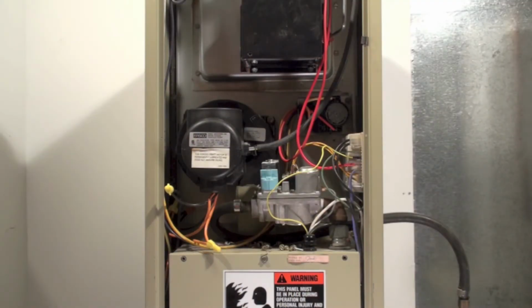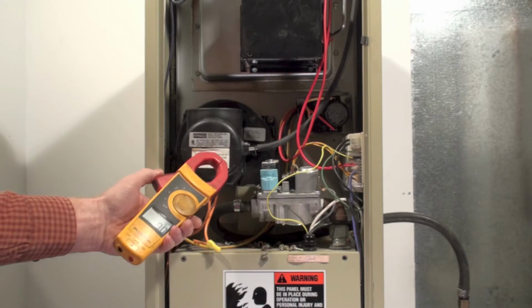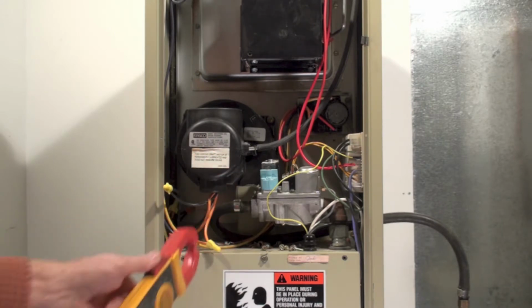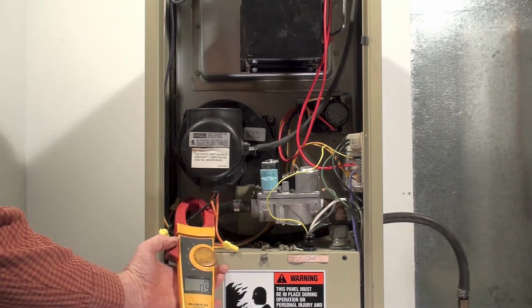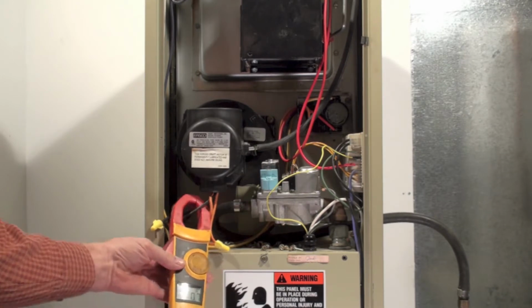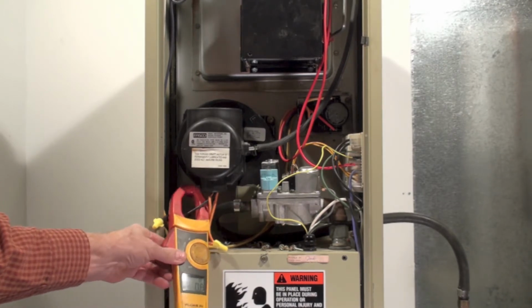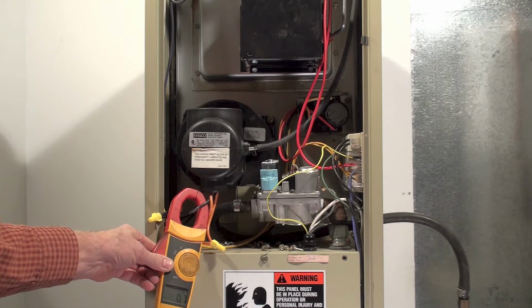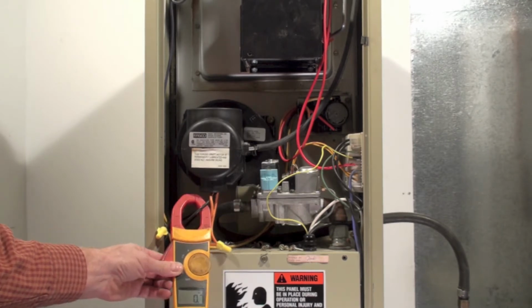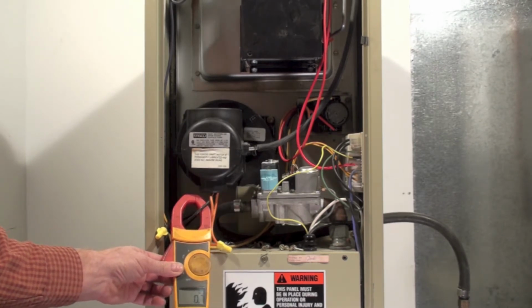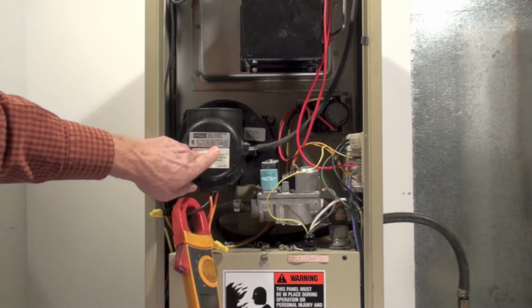Okay, for service on this GUA, I'm not going to go over everything. I'd reference you back to 80% service for a lot of it, but just a couple things maybe a little bit different on this thing. Once you've got that draft motor running, check your amp draw. Now this looks like it's drawing about 7/10 of an amp, and it's rated at 1, noted right there.